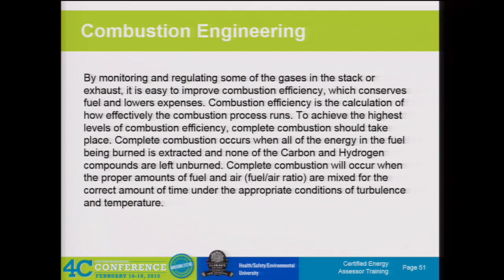By monitoring and regulating some of the gases in the stack or the exhaust, it's easy to improve the combustion efficiency, conserve fuel, and lower expenses. The monitoring we talked about in the energy assessment—and that we'll talk about more in the boiler tune-up—is monitoring that chemical reaction and seeing how our boiler is set up and what performance we're getting out of the combustion scenario. Combustion efficiency is the calculation of how effectively the combustion process runs—how we're converting our fuel to the required energy we need.